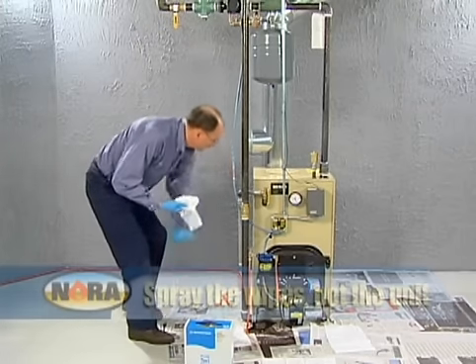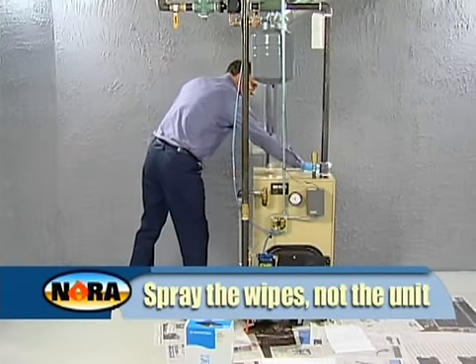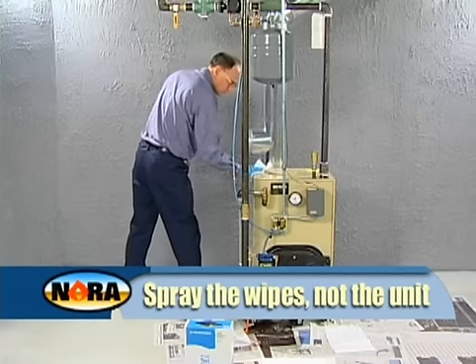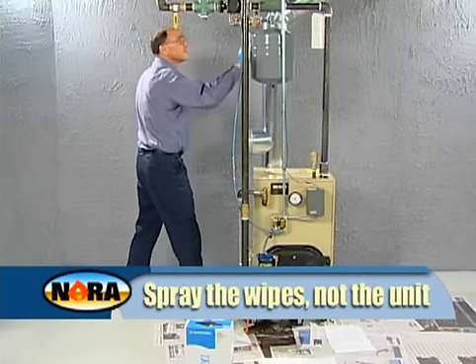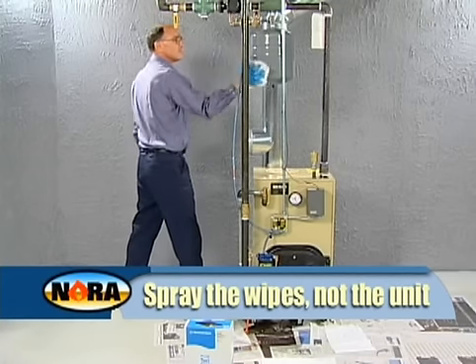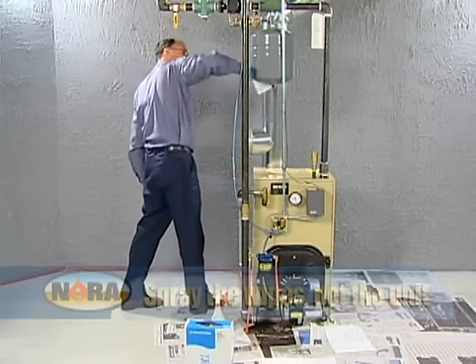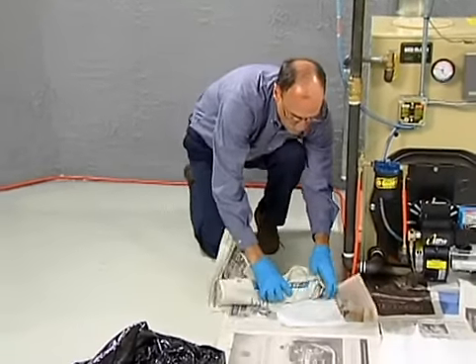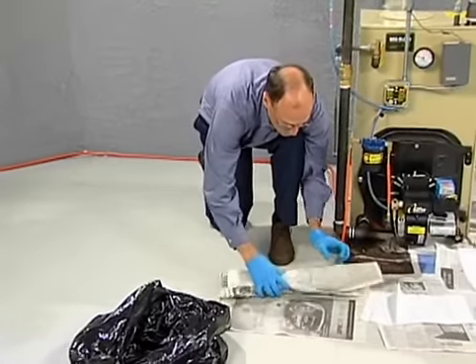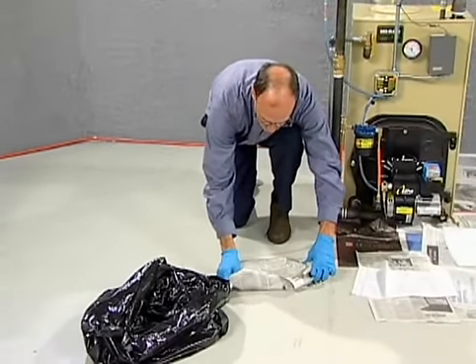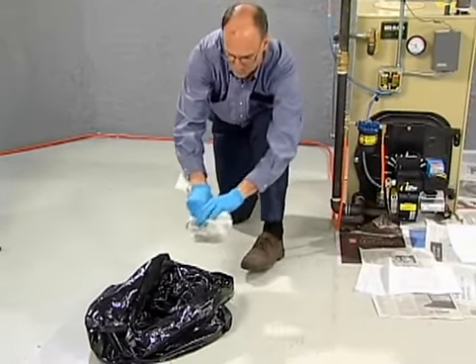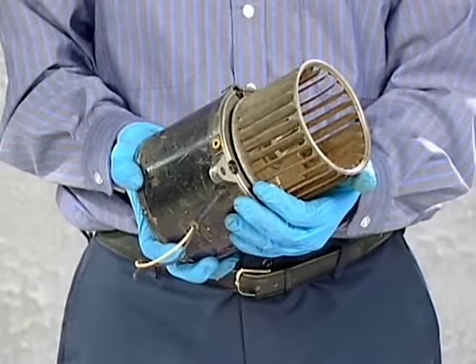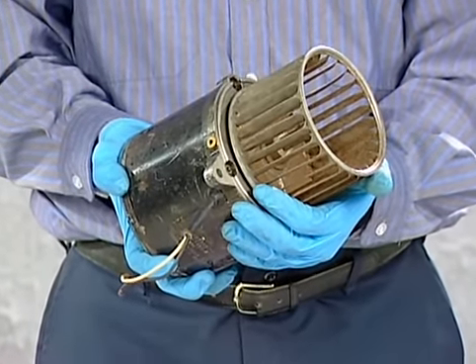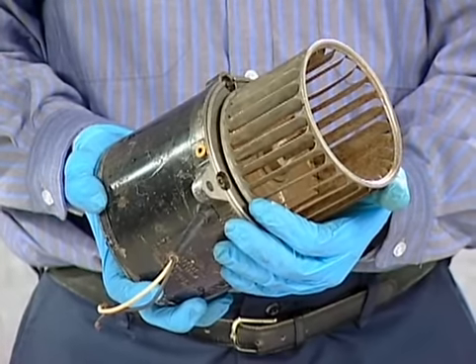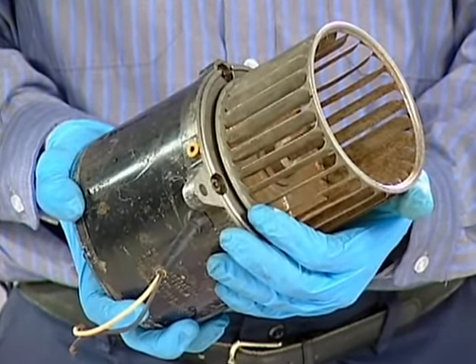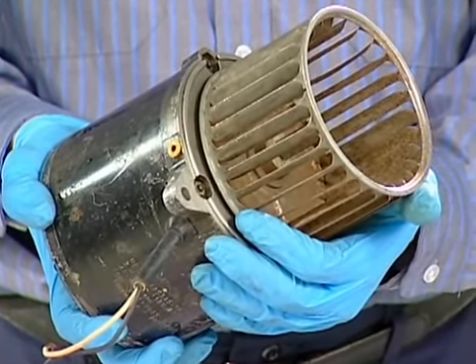Spend a few moments cleaning up. Wipe and clean all of the external surfaces of the burner, boiler, or furnace and work area. Use only clean rags so you don't leave behind the smell of oil. Use a garbage bag to remove the old parts, newspaper, or drop cloths so that nothing can fall out on your way back to your service vehicle. You should even take away any old parts that may have been left there by previous technicians, unless the owner wants to keep them. Be sure to check.